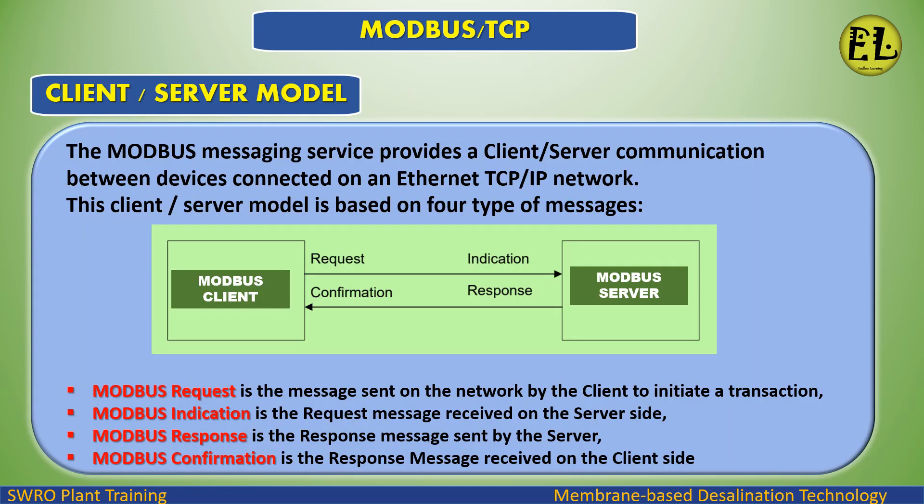The client/server model: The Modbus messaging service provides client/server communication between devices connected on an Ethernet TCP/IP network. This model is based on four types of messages: Modbus request (sent by the client to initiate a transaction), Modbus indication (the request received on the server side), Modbus response (sent by the server), and Modbus confirmation (the response received on the client side).